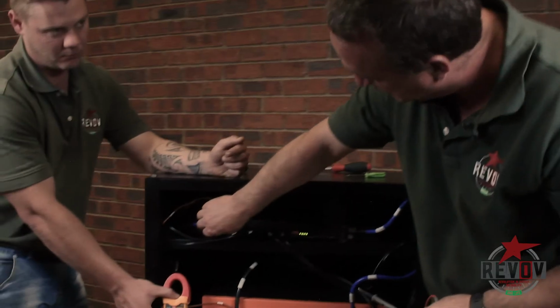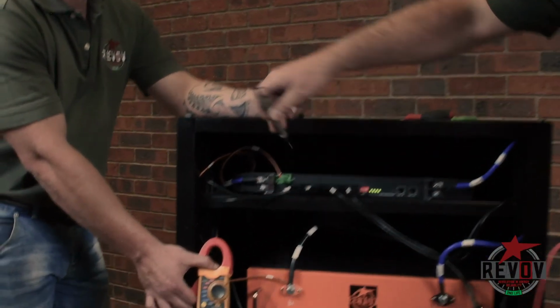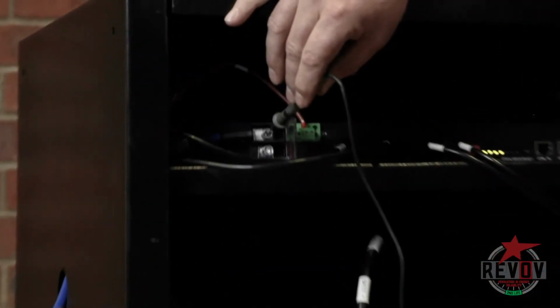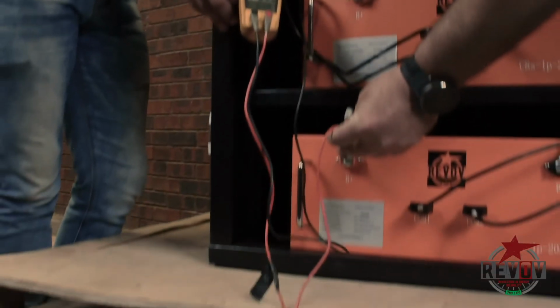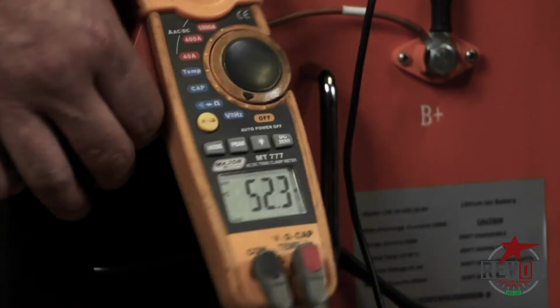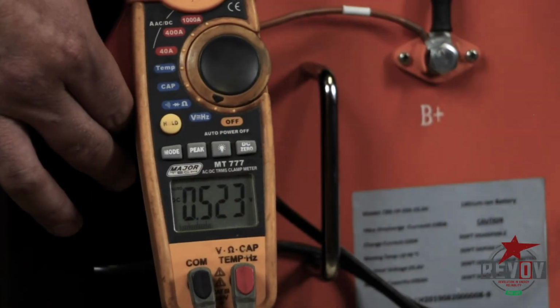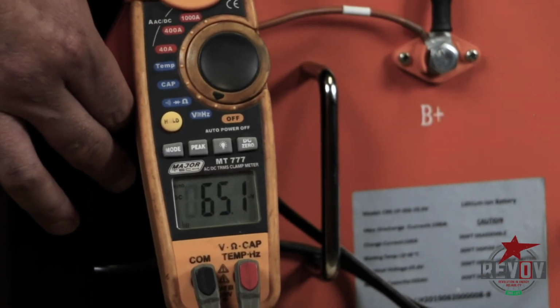What we would do is open up the P minus, which is going to the load. We would put that on there, and put that on the battery down at the bottom, and that should also give us 52.3, which means the BMS is open, the relay is open, and the BMS is operating.